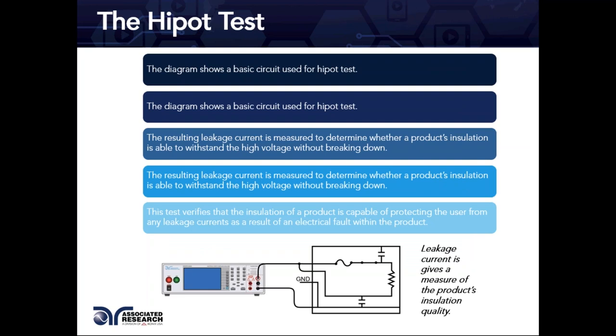Looking at the basic circuit diagram on the slide, the product under test is on the right and the Hipot tester on the left. The result of a Hipot test is always measured in terms of leakage current — in milliamps or microamps, depending on whether it's an AC or DC Hipot test. The leakage current determines whether the product's insulation can withstand high voltage without breaking down.